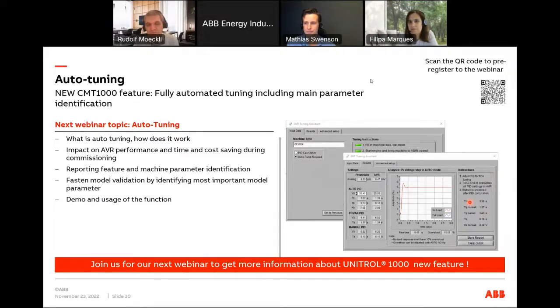So, if the generator has a shunt supply, that means your supply of the AVR comes directly from the output of the generator. When you have a short circuit in the net, you lose this power supply. In these terms, you have installed CTs on the generator which then provide energy to the field. But the problem is these CTs typically must be designed in the right way, and not everybody knows how to do that—it's very specific to the machine.